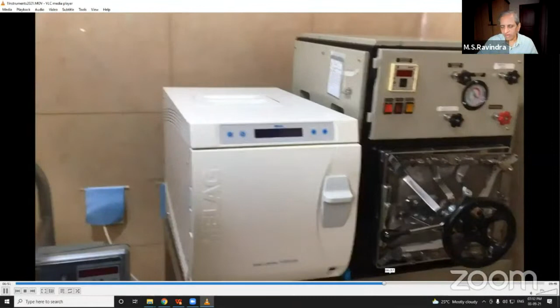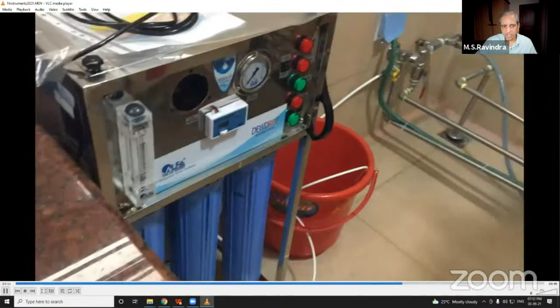That's a Melag autoclave. And Melag autoclave has got both the flash setup as well as the full B autoclaving cycle, but we use only B cycle. We never use flash autoclave in our operation theater because B autoclave full cycle is always better than the flash autoclave. That's a water supply to the autoclave. We have a horizontal autoclave, which is a B class autoclave, and that's got a nano controller.